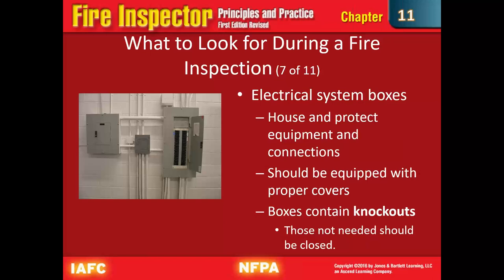Boxes contain knockouts — the little disks around the inside of the breaker box. In older construction you may see some that have been knocked out for wiring that was later removed, or where an electrician knocked out the wrong one. Make sure those are enclosed — there are little plugs that can be put in there if a knockout was removed and not needed. Anything that's not supposed to be in that breaker box needs to be kept out.